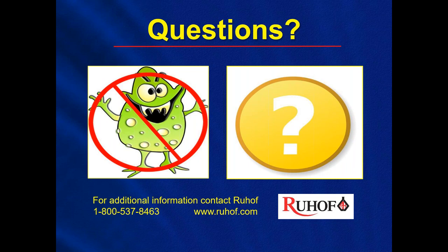Hope that helps. Okay, and another scope question. What are the scope drying requirements? Scope drying, again, you're going to have to go by manufacturer's IFUs. And if you're using a cabinet for drying, then you're going to follow the cabinet manufacturer's recommendations also. Some of them have circulated filtered air going through them. Again, that's all based on manufacturers. And the drying should be part of the IFUs by the scope manufacturer for the entire cleaning process.